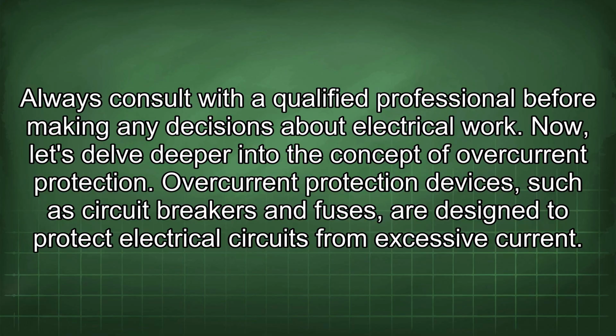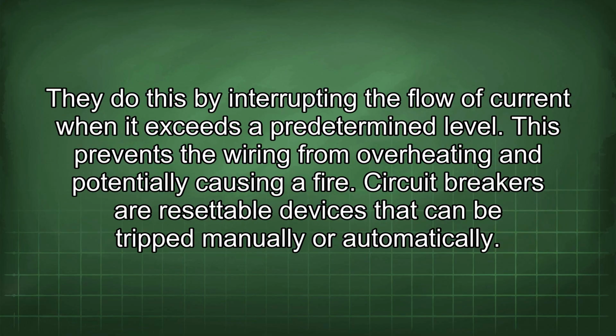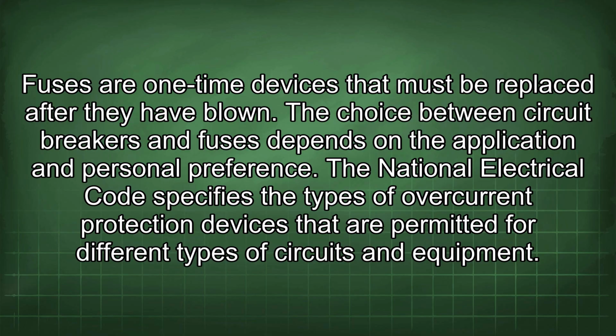Now let's delve deeper into the concept of overcurrent protection. Overcurrent protection devices, such as circuit breakers and fuses, are designed to protect electrical circuits from excessive current. They do this by interrupting the flow of current when it exceeds a predetermined level. This prevents the wiring from overheating and potentially causing a fire. Circuit breakers are resettable devices that can be tripped manually or automatically. Fuses are one-time devices that must be replaced after they have blown. The choice between circuit breakers and fuses depends on the application and personal preference.